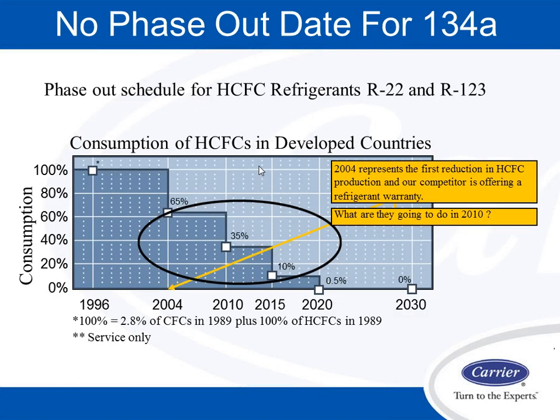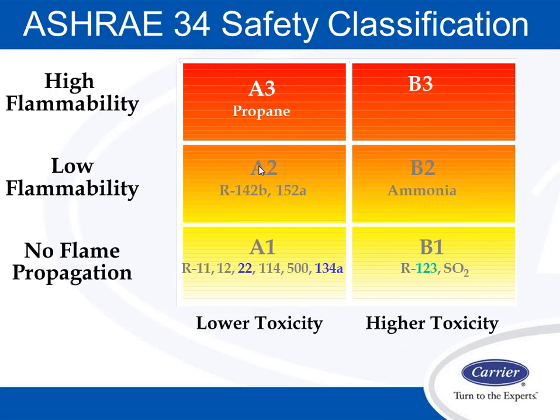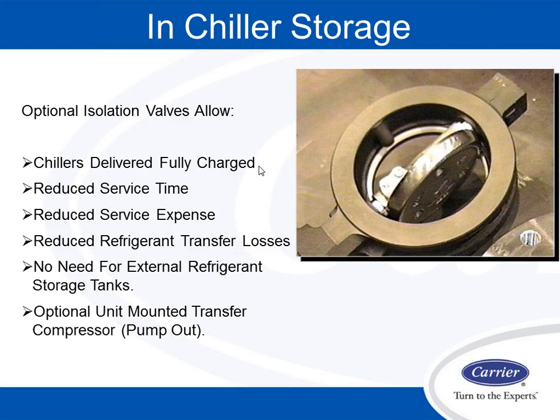Again, 134A, showing the phase-out dates. I'm not going to go in depth on this, but basically that's why we feel there's no phase-out date, so that's the right refrigerant. From a safety standpoint, 134A is low toxicity with no flame propagation, whereas 123 is higher toxicity with no flame propagation. In-chiller storage: we ship every one of our chillers with an isolation valve package on it, so you can store the refrigerant in either the cooler or condenser to do service work. Saves time, reduces service expense.